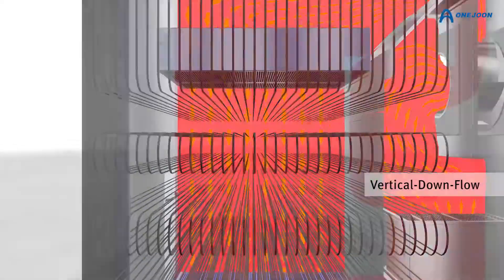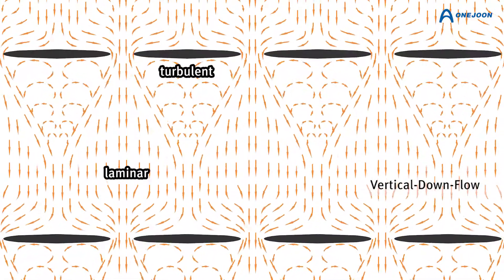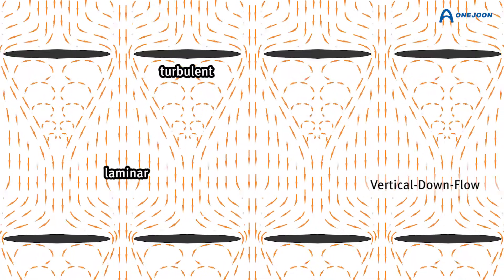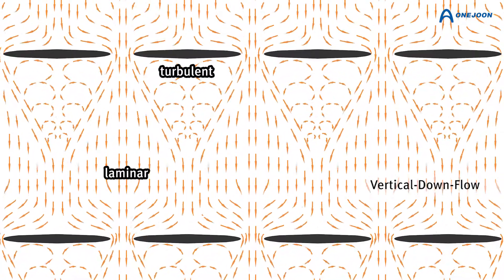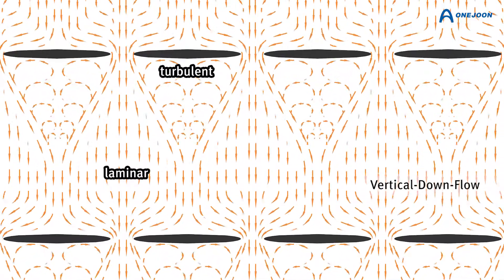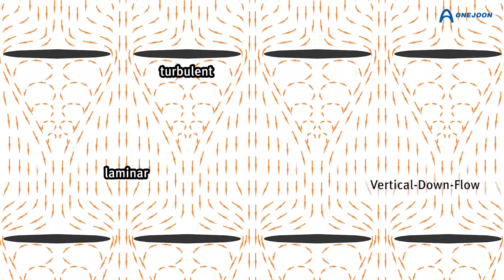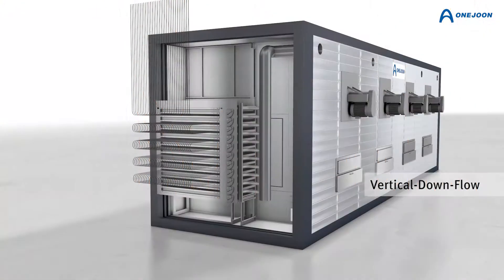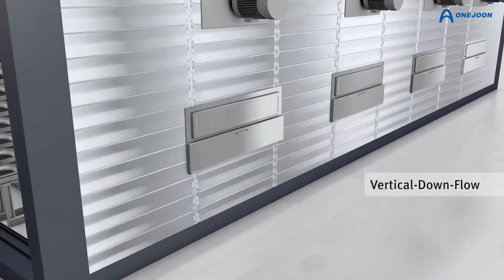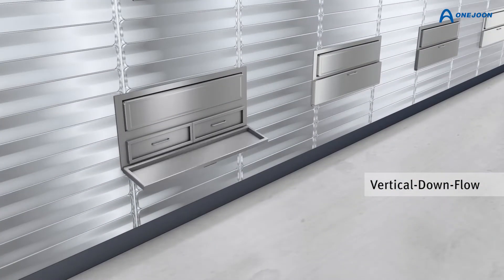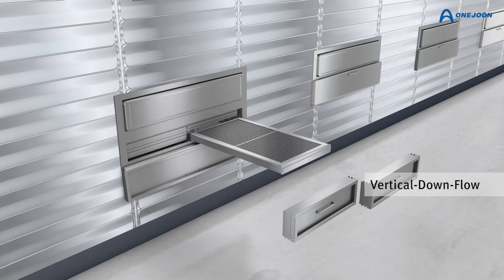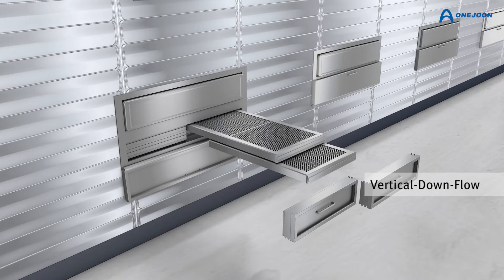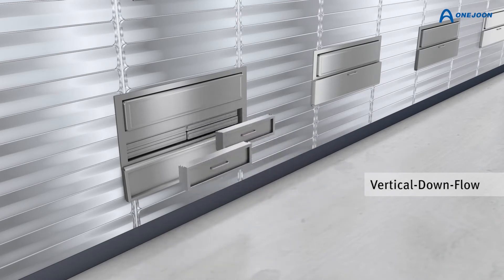The vertical downflow air delivery system is typically the preferred airflow technology for small tows. The turbulent airflow at the tow provides the safest control of the exothermal reaction, resulting in the shortest oxidation times. Filter elements in front of the heating devices ensure that loose fiber filaments are removed from the process airstream, preventing the blocking of downstream components. The two-stage filter configuration allows for ease of servicing during fiber production.